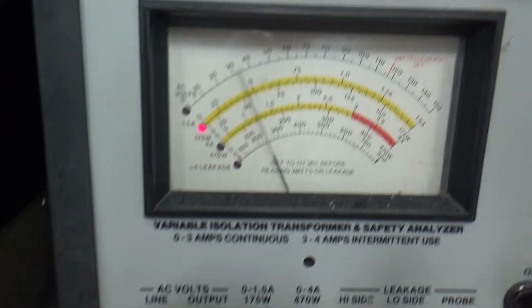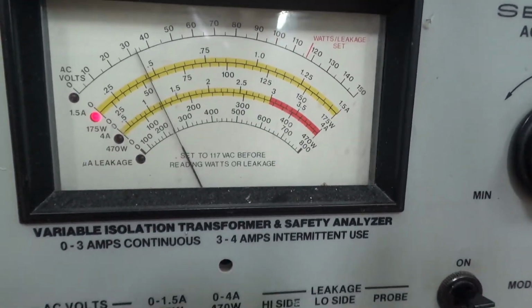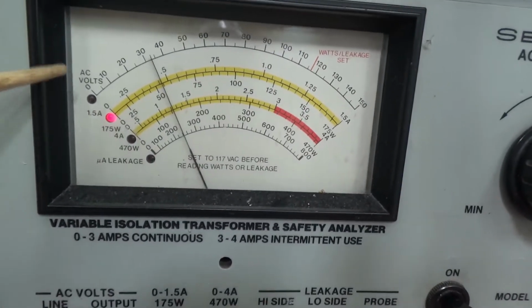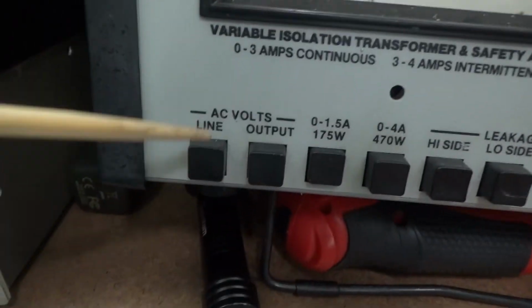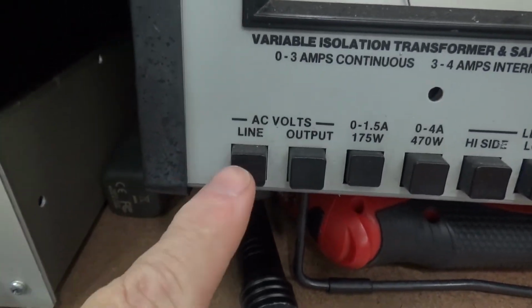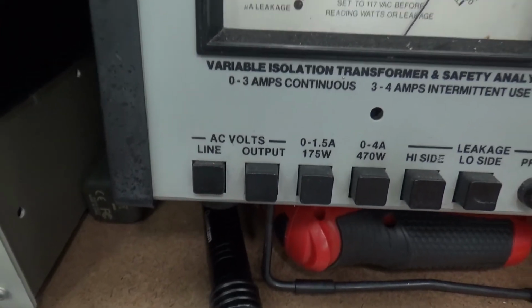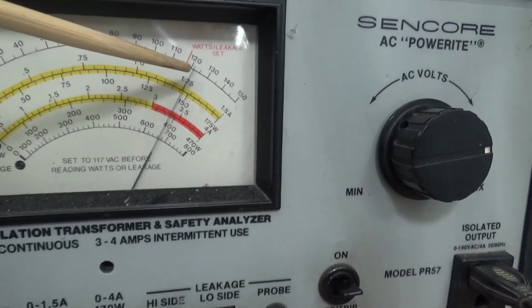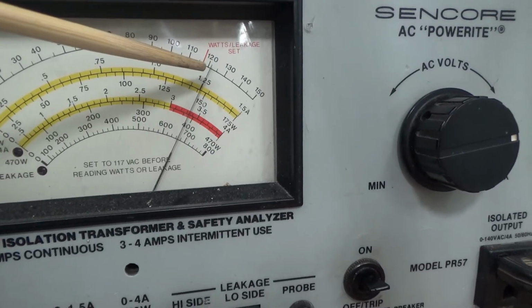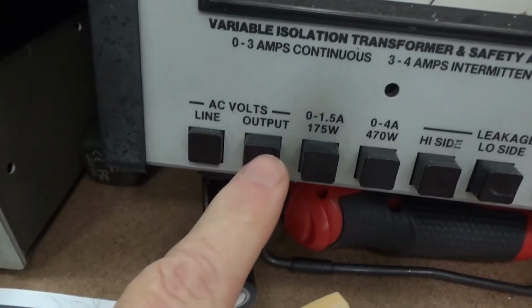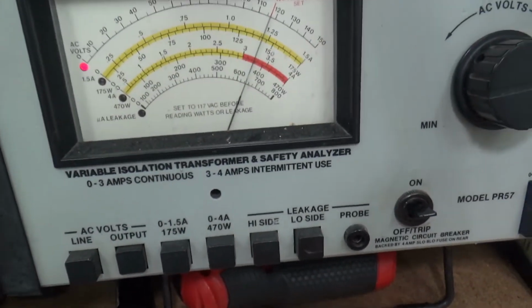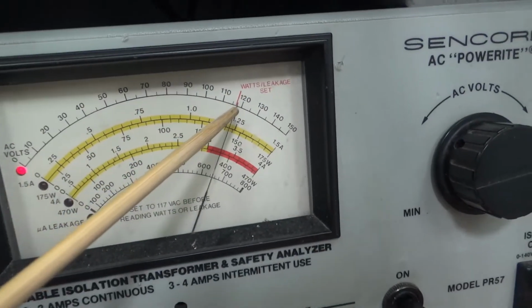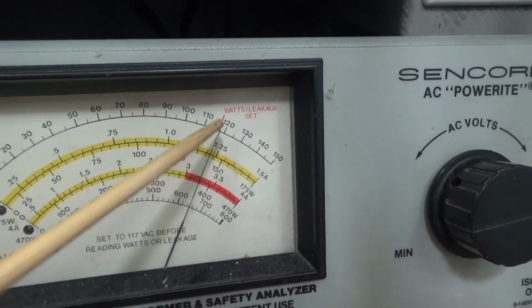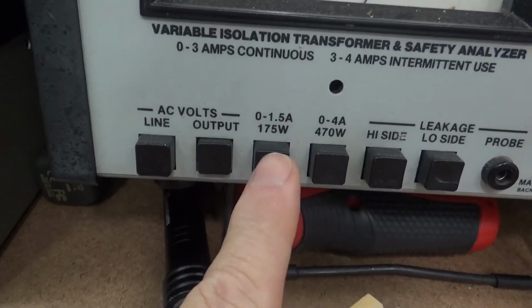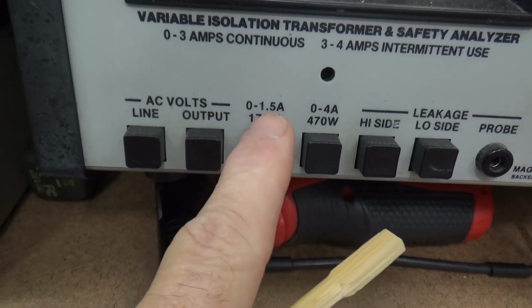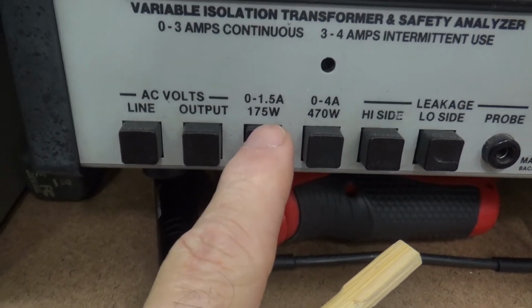Let's go back to this right here. There's your scale. And let's say here, this is your AC volts out. What's selected, see the AC volts. So if I push this right here, this is line. This is telling me what my line voltage is right there, 121 volts AC. If I select output, it's telling me what my output is. I have it adjusted to this red line. It says watts leakage set. Well, what do you need that for? Well, you push this button. 0 to 1.5 amp scale, 175 watts full scale.